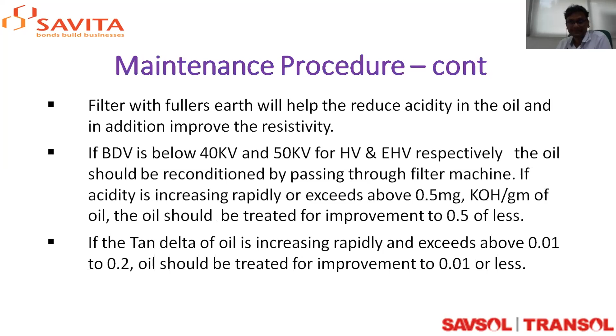If the tan delta or power factor of the oil is increasing rapidly and exceeds 0.01 to 0.2, the oil should be treated for improvement to get the tan delta value less than 0.01. The procedures will be similar. There are certain pads available in the market. There are certain Fuller's earths, and one can go for those treatments. Next slide.